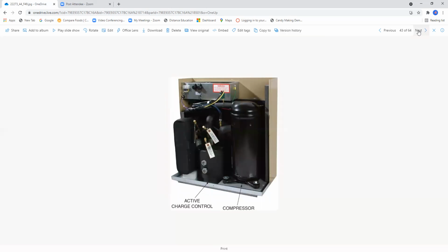Okay, here this looks like a condensing unit. You can obviously see the compressor over to your right, and you see the other parts of this refrigeration heat pump system. Notice that it's very compact. It's not that hard to work on. This is found on page 1349 of your textbook, and this is figure 44.49, the internals of a heat pump compressor showing the active charge control with 2 sight glasses. So the sight glasses, kind of curious, where are those? Oh, there they are right there. So we can actually see how much refrigerant is inside the system here, high and low.